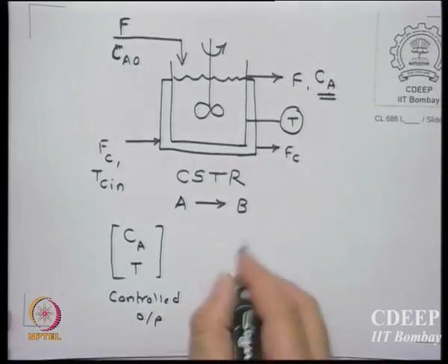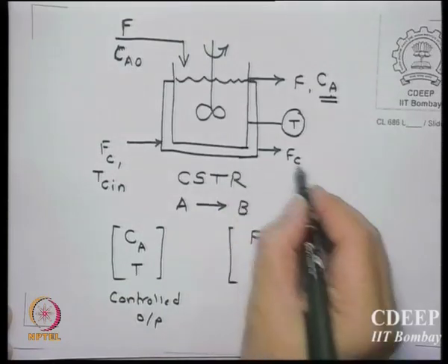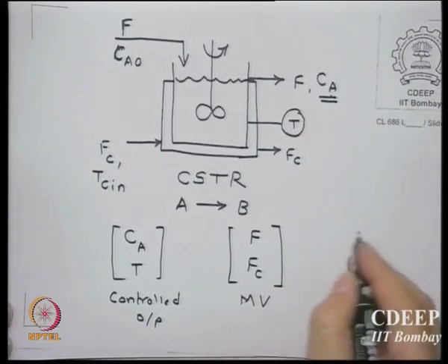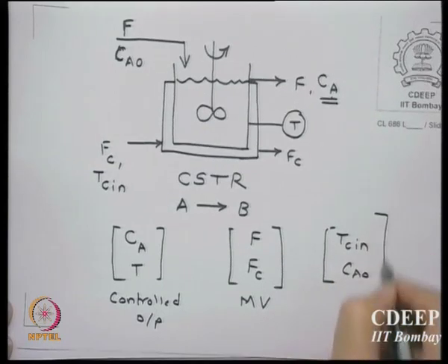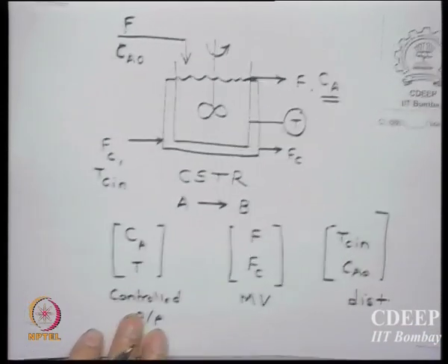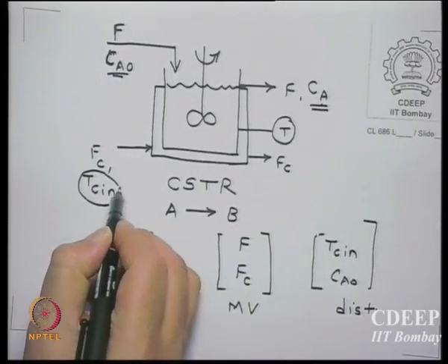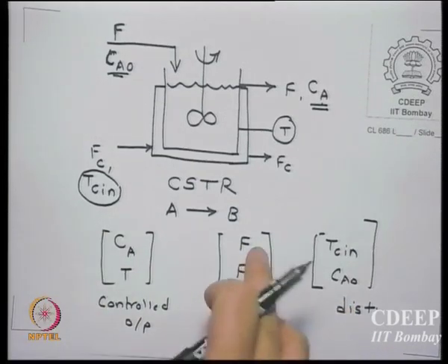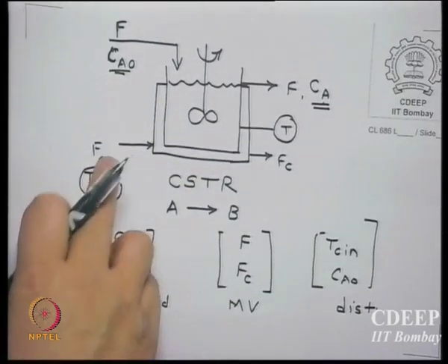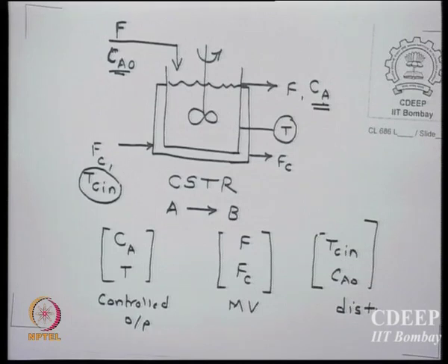The controlled outputs are concentration and temperature - these are the two controlled outputs. The two manipulated variables are the inlet flow rate and the cooling water flow rate. The disturbance variables are the concentration of the feed coming in and the inlet temperature of the cooling fluid, which can fluctuate.